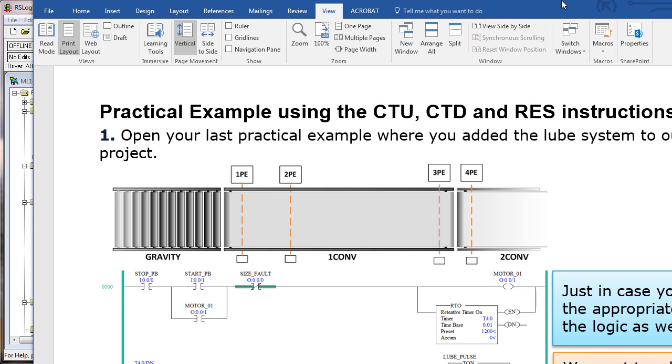In conveyor motors, we know six pieces of information. We know that we've turned one conveyor on or off and two conveyor on and off. That's two pieces, two bits. Then we have four photo eyes. With these four photo eyes, we know whether or not there is something blocking the optical path of 1 PE and/or 2 PE and/or 3 PE and/or 4 PE. So that's six bits of data that is our data structure. In other words, we're creating a structure of data that represents our process. In this case, we've got six bits to work with, two outputs and four inputs.